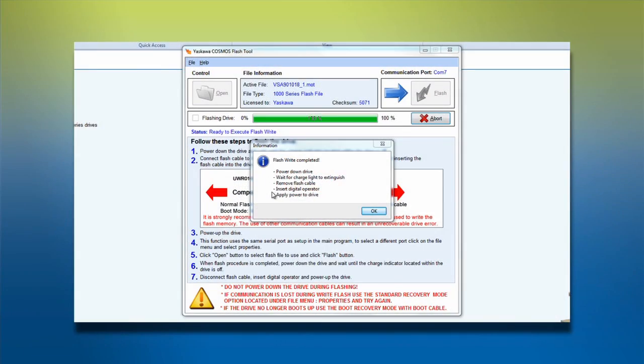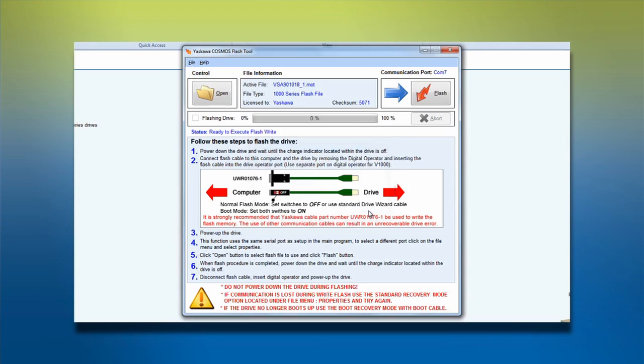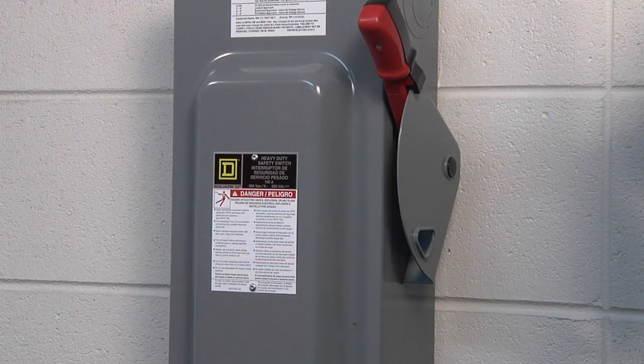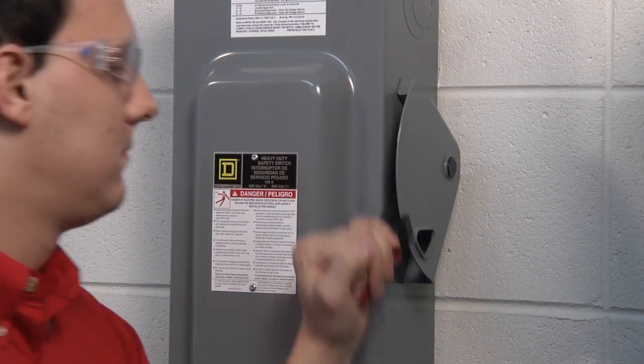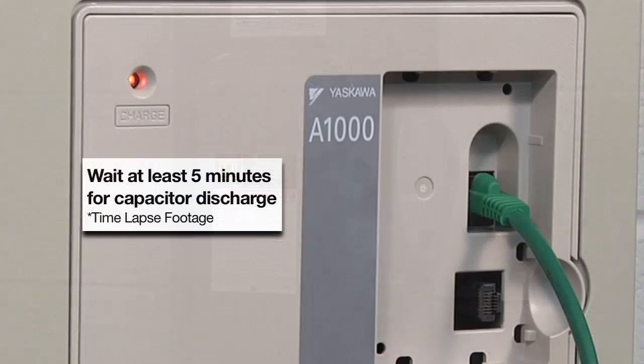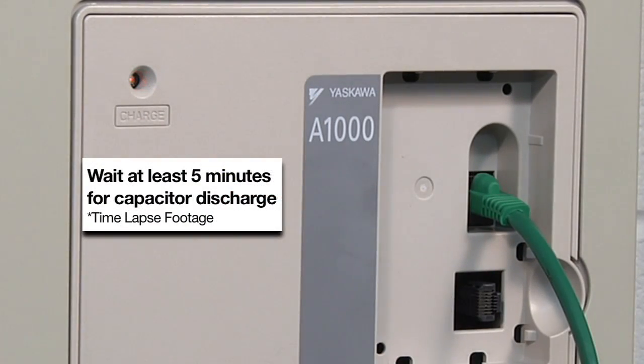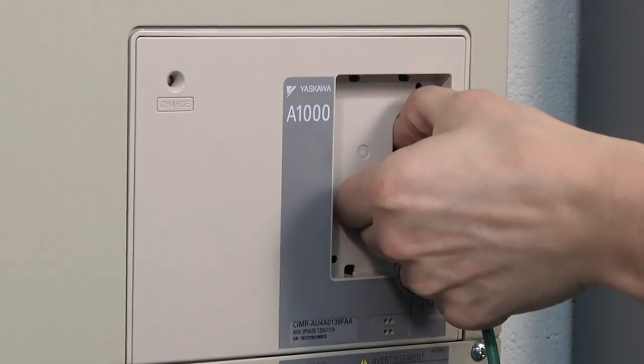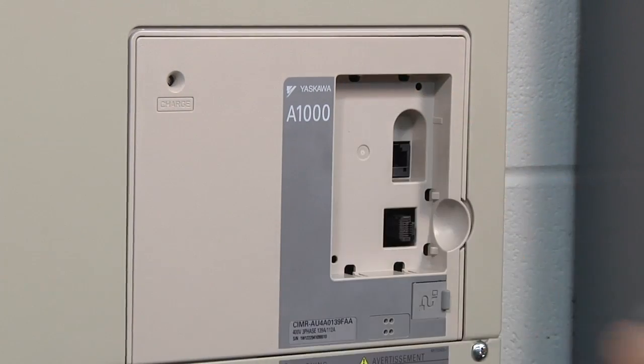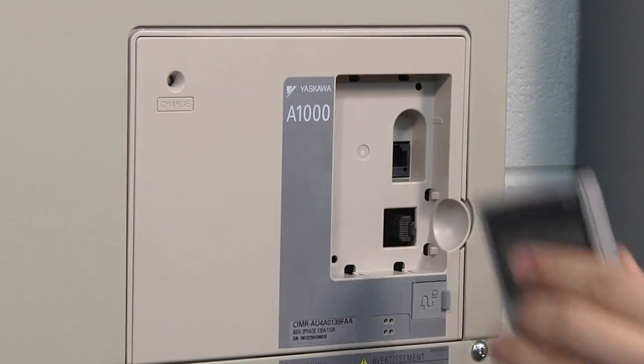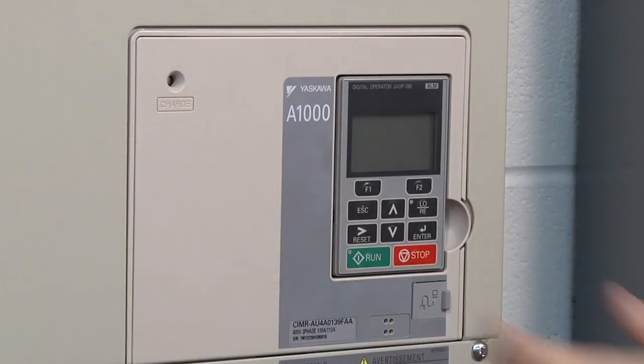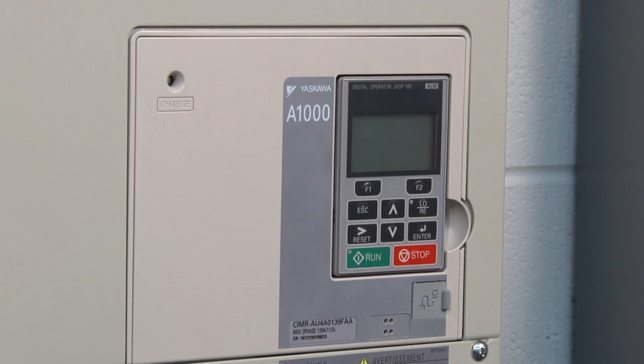After the flashing process is completed, follow the steps in the dialog box on the computer screen. Power down the drive, wait for the charge light to extinguish, remove the flash cable, insert the digital operator and restore power to the drive.